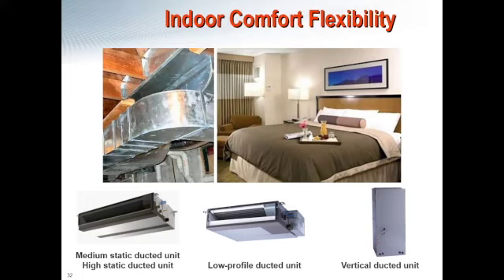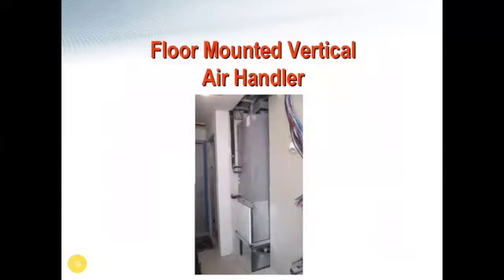One good thing to know about almost all VRF vertical ducted units is that they can be installed horizontally as well. They are truly a multiple position unit. So that's one thing to take into account. They're great when you have a ducted application and you need a little bit more static pressure to overcome long duct runs or anything like that. They're a very good option. This is just a picture showing the floor-mounted vertical air handler in its typical application. I'm not going to get too much into this, but just remember it can be mounted either way, left, right, up or down discharge. So it's extremely flexible as far as the installation goes.